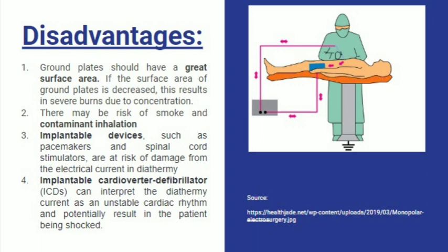Second, there may be a risk of smoke and contaminant inhalation, as the contaminant burned by the diathermy needle vaporizes and may be inhaled by the operator. Third, implantable devices such as pacemakers and spinal cord stimulators are at risk of damage from the electrical current in diathermy, as it passes from the needle into the patient's body and through the body to the ground plate.